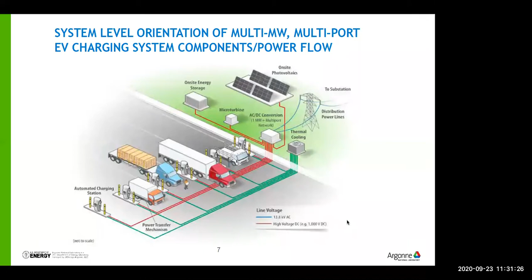So just reminding people, the power has to get from where it is to where it needs to go. That's what's going on in this NREL testing event - these yellow circles. How do we get the cable to reach that far, yet carrying 3,000 amps, and not accidentally interrupting up to 4 megawatts? So again, arc flash is a big deal.